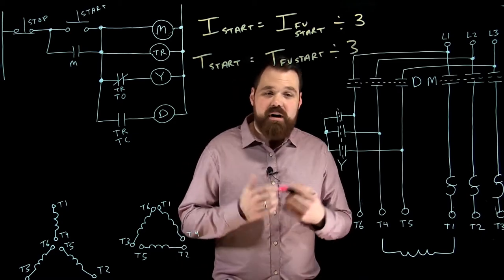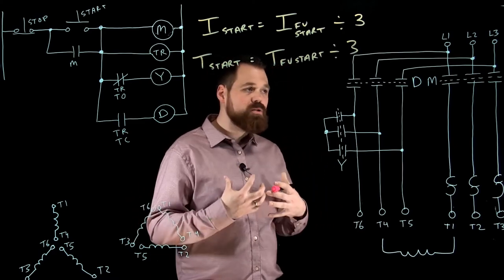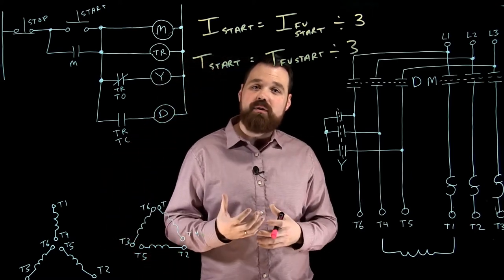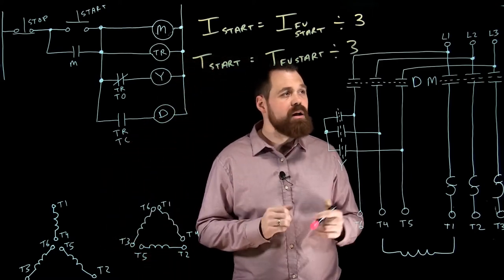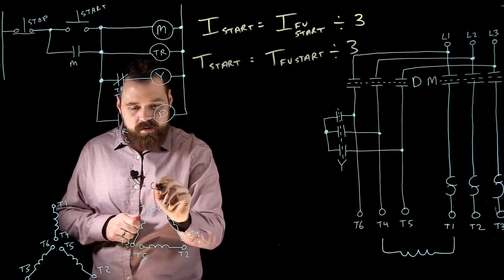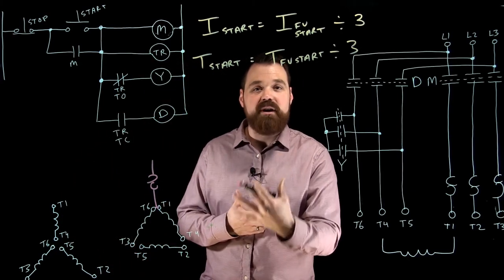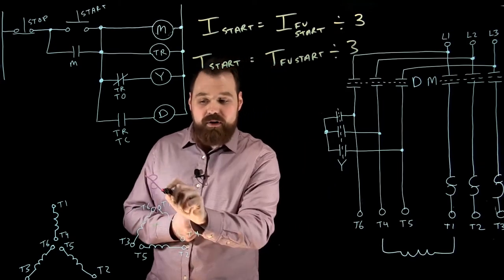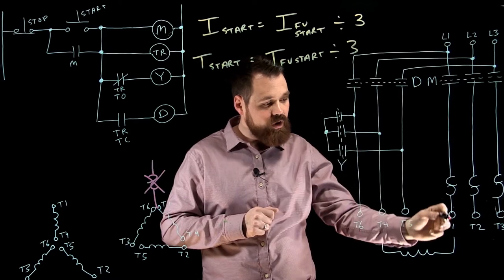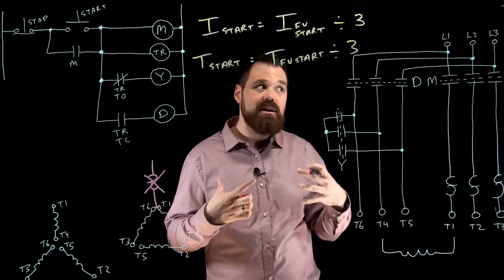The last thing I want to talk about is very different and important with a Y-delta starter. It has to do with where those overloads are located. When we think about this, when I was running in delta, because we only care about the overloads when our motor is actually running, we know normally in delta, if we were to have an overload in the line, it would see line current, which is what the nameplate value is. However, in this case, our overloads only see the current that's going to flow through one phase at a time, not splitting off and going into two.